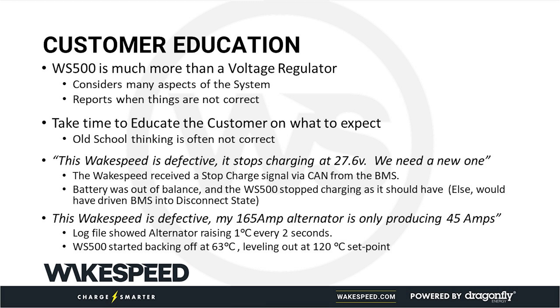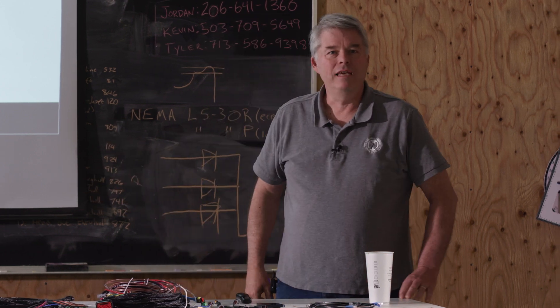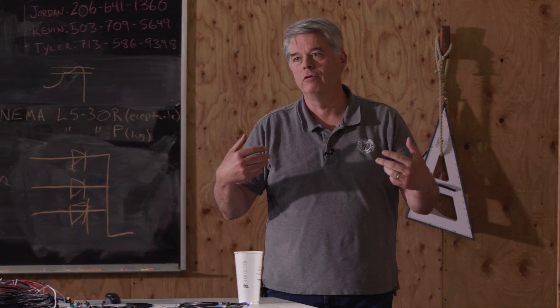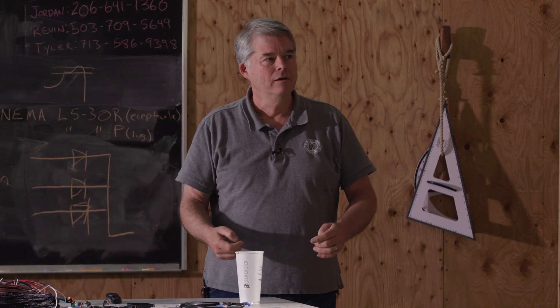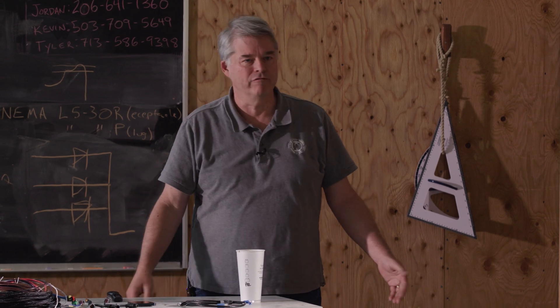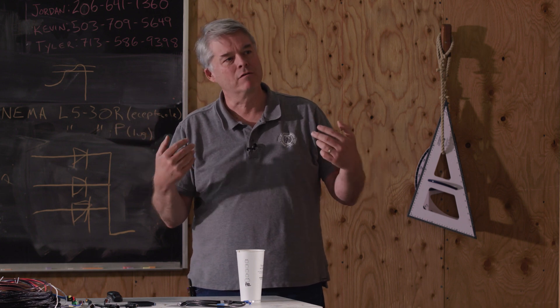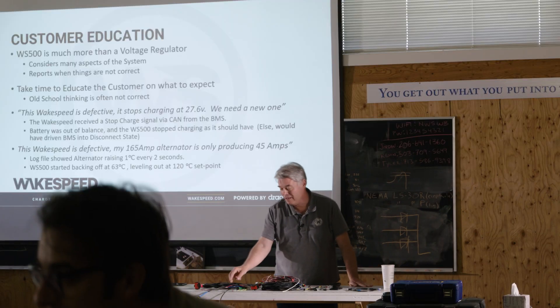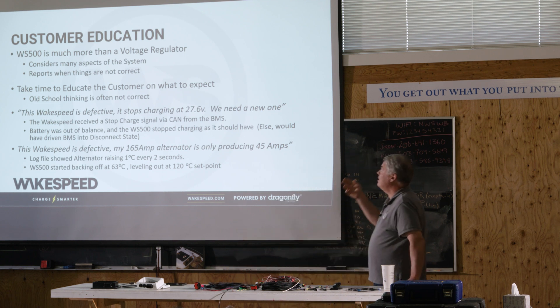We're now going to enter the phase of real-world things that we've observed. Do you have any questions up to this point? Because we're really starting to wrap up. These are some of the real-world experiences we've found that are problems with the Wakespeed — and we've talked about a few of them. It's a very configurable product. People configure it wrong. People go into expert mode and reconfigure it. Most of them are configuration issues. I think 60% of the calls that get to me are configuration, and 40% they haven't hooked all the wires up. Hook up all the required wires, please.